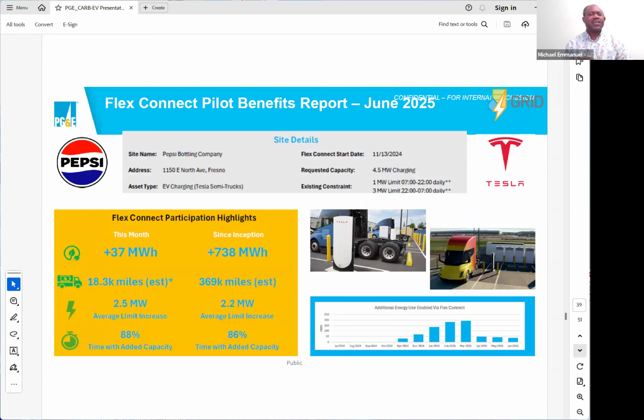This next slide is a real-life scenario of a site that came online, belonging to Pepsi Bottling Company. As shown in the site detail, the requested capacity was 4.5 megawatts. But this site has an existing constraint: it's only allowed to operate with 1 megawatt between 7 a.m. and 10 p.m. daily, and 3 megawatts from 10 p.m. to 7 a.m. daily. Depending on utilization, this is definitely a constraint that would discourage any developer from coming online. But with flexible service connection, let's see how much we can unlock for them.